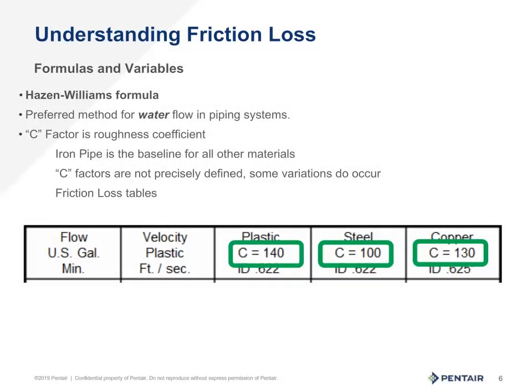One key factor is the C value of the material the water is flowing through — this is the smoothness factor. Steel, being the standard in the last century, is the standard on which other pipes were compared, and thus steel is graded 100. The smoother the material compared to steel, the higher the number will be. The rougher the material compared to steel, the lower the number will be.